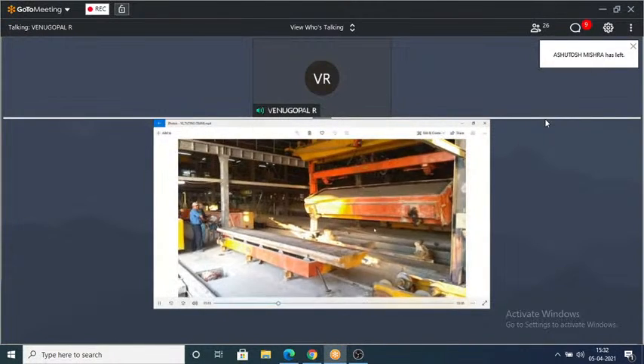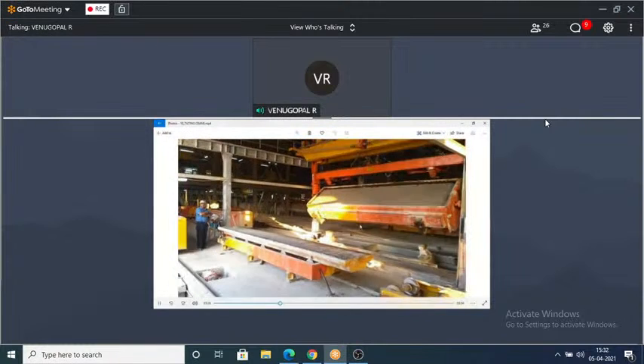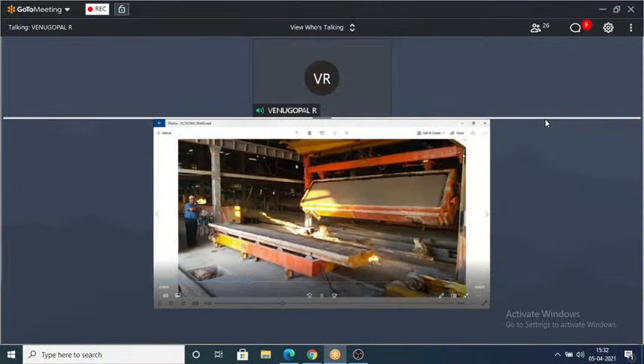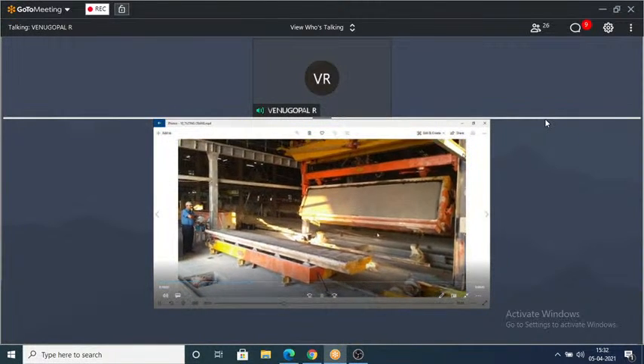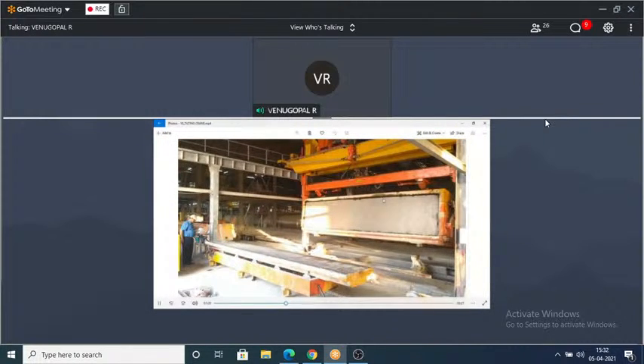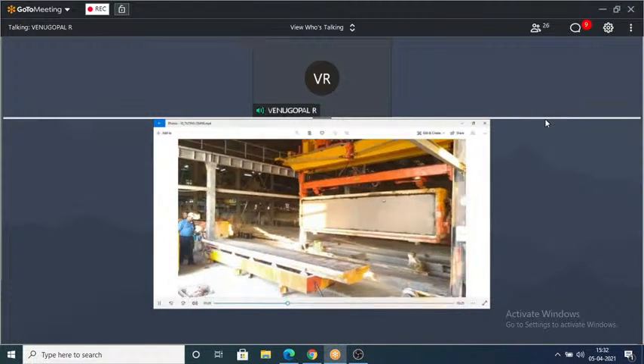So there's a lot of calculation involved. To lift 8 tons in 1 minute, I need a different size of motor. Same 8 tons, if I have to lift in 4 or 5 seconds, I need a much more powerful motor. So how do you calculate that?